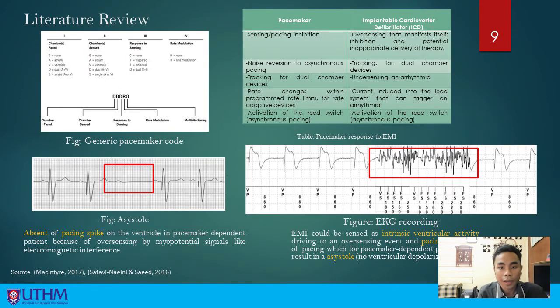First of all, a pacemaker has a generic code that can be programmed depending on the patient's condition. The first code is for pacing, the second is for sensing electrical signal, and the third is for triggering or inhibiting pacing at chamber 1 based on the signal received from the second chamber. If it is sensing an artifact signal or myopotential in that area that came from unwanted physical activity or EMI, it can give several responses in the pacemaker, such as sensing and pacing inhibition or noise reversion to asynchronous pacing.